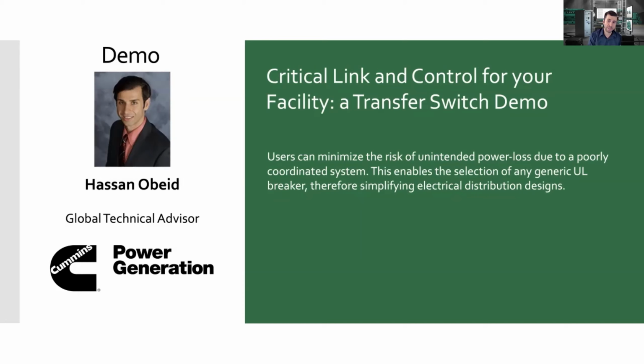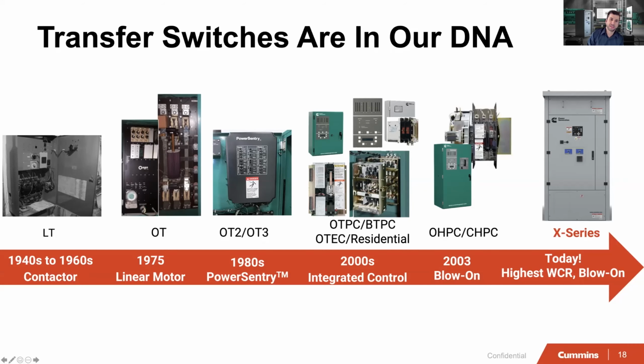That's why Cummins has designed the next generation of reliable power transfer equipment, the Power Command X Series transfer switches. Transfer switches have been in Cummins DNA for over 80 years, back from the 40s when we started designing transfer switches during WW2. We've had numerous innovations and evolutions along the way, from the linear motor to having advanced controls to what we call today the blow-on technology, which uses electromagnetic force and a mechanical force to hold the transfer switch closed if there's a fault or under normal conditions. And today we took that technology that we invented in 2003, and we brought it to what we call today the X Series transfer switch, which has the highest WCR, withstand and closing rating, and it uses the blow-on technology in the industry.